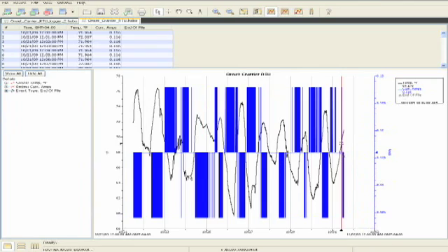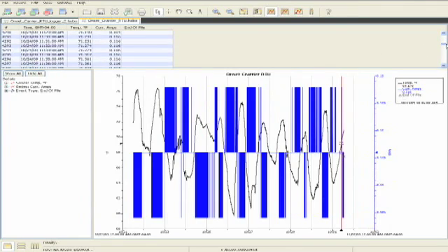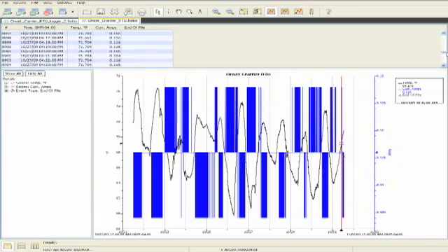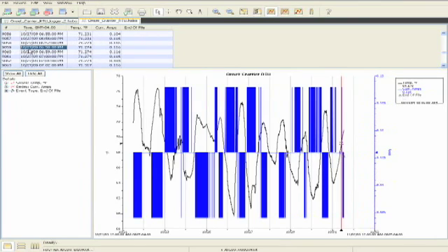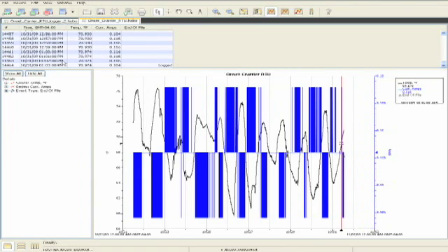Most of the time we'd be looking for supply air temperatures during a call for cooling or heating from this particular graph. Since we don't have that, we don't have anything on the heating end either, with the supply temp being at a high of 76. We would have seen something in the 120 degree range if the unit called for heating at any particular point. So this goes down, logging every minute all the way to the end of the log.